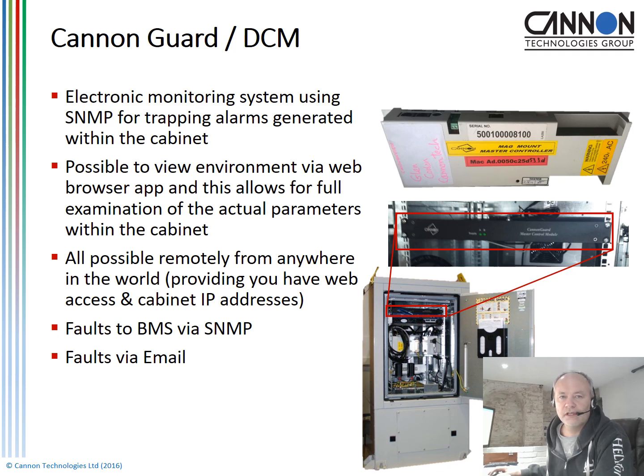So we also have developed a product called Cannon Guard. This allows you to monitor remotely via Ethernet connection really what's going on inside the cabinet. You can monitor temperature, humidity, for example. You can have smoke detection alarms in there. You can have detection to see if a door has been opened on the cabinet. You can have additional things like a CCTV camera installed into the cabinet, which then will obviously provide a feed if somebody does open the cabinet to break in. We can have fire suppression systems installed into the cabinet, all those type of things.